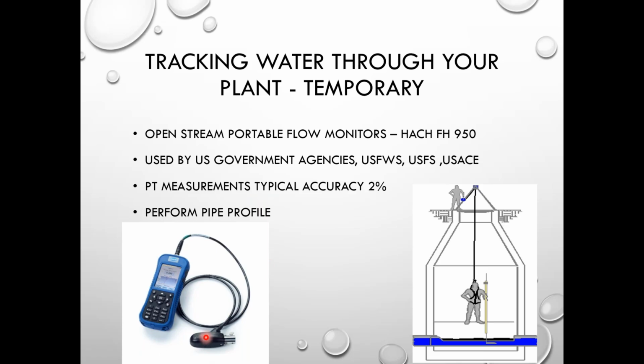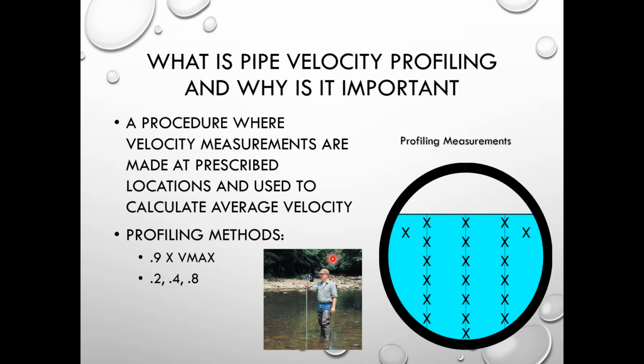The accuracy of the electromagnetic velocity sensor in there is about 2%, and it just simply has a little thumb nut here, and we can mount this onto a pole, what we call a staff gauge. It'll have 1-inch increments or 1 meter increments on that staff gauge to give you depth, and you just move it up and down through the channel to do a pipe profile. So what is a pipe profile? It's going in and it's grabbing various velocities through your pipe, right? And it's determining what the average velocity is in the flow.